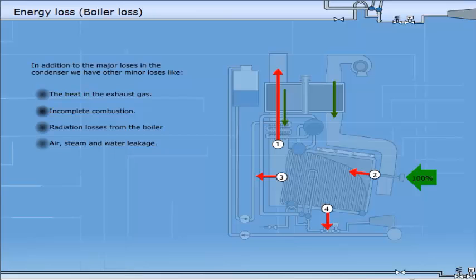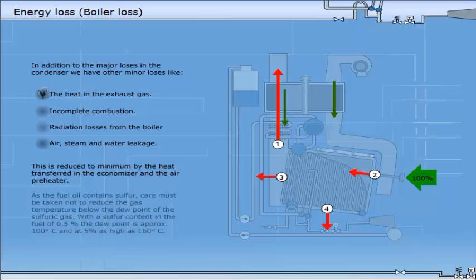Air, steam and water leakage. This is reduced to a minimum by the heat transferred in the economiser and the air preheater. As the fuel oil contains sulphur, care must be taken not to reduce the gas temperature below the dew point of the sulphuric gas. With a sulphur content in the fuel of 0.5%, the dew point is approximately 100°C and at 5% as high as 160°C.